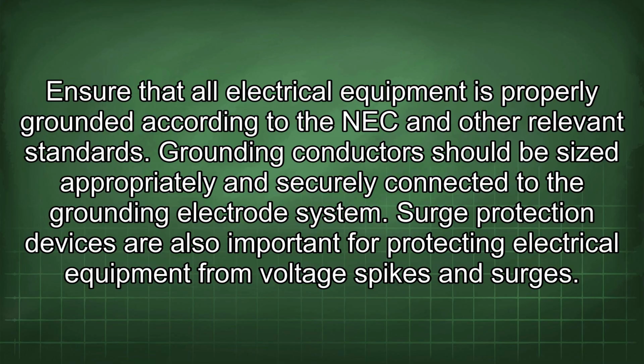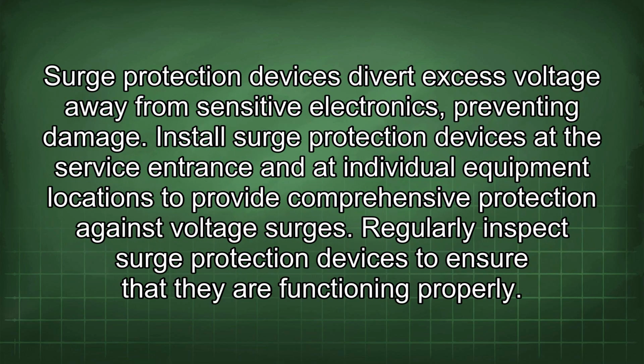Grounding conductors should be sized appropriately and securely connected to the grounding electrode system. Surge protection devices are also important for protecting electrical equipment from voltage spikes and surges. Surge protection devices divert excess voltage away from sensitive electronics, preventing damage. Install surge protection devices at the service entrance and at individual equipment locations to provide comprehensive protection against voltage surges.